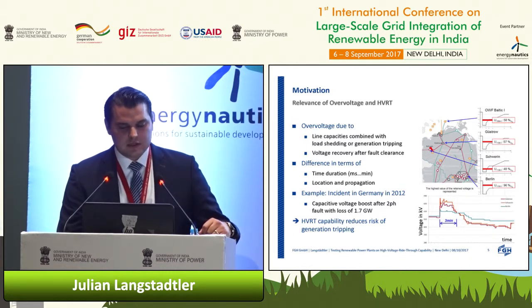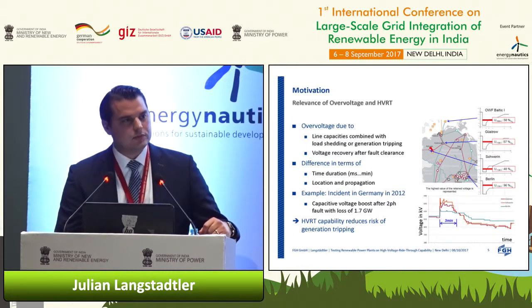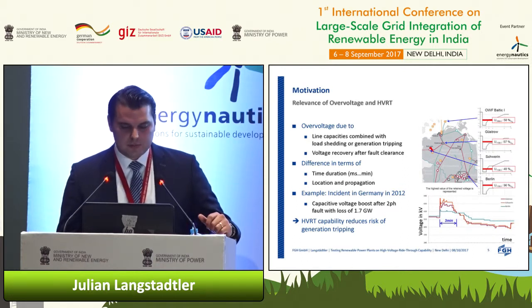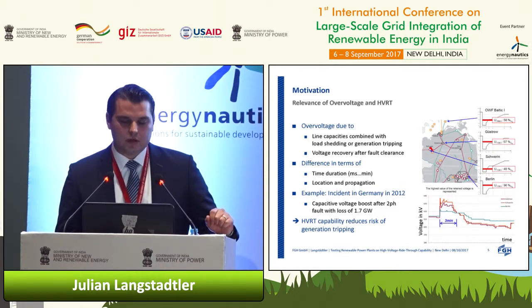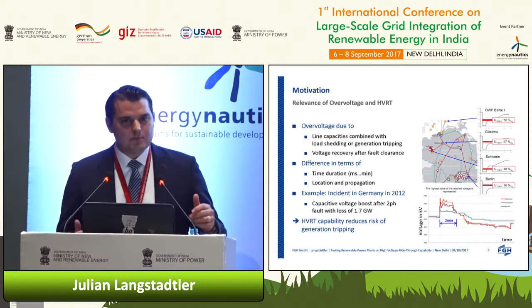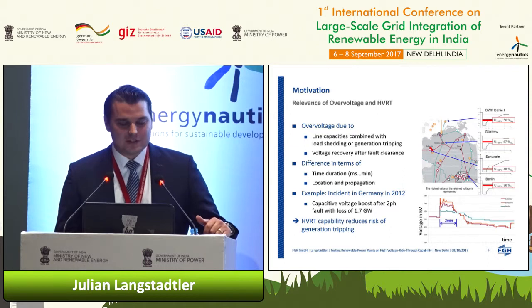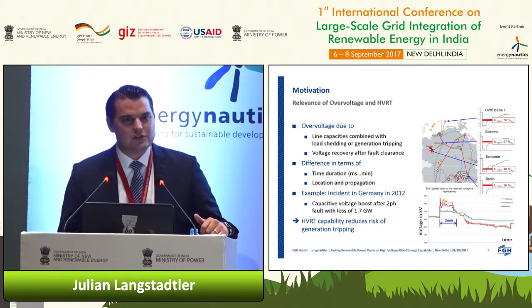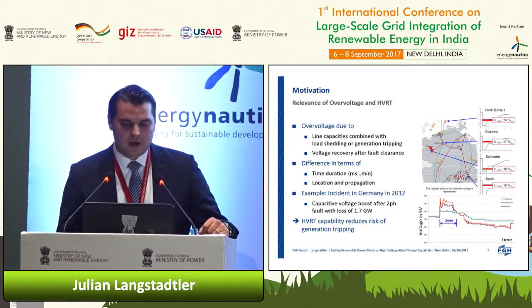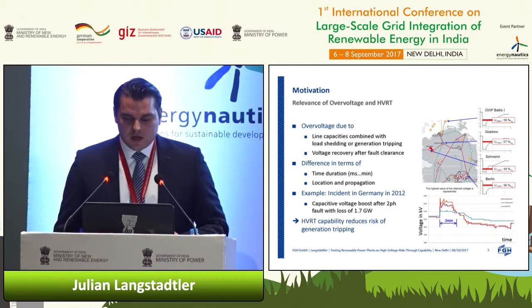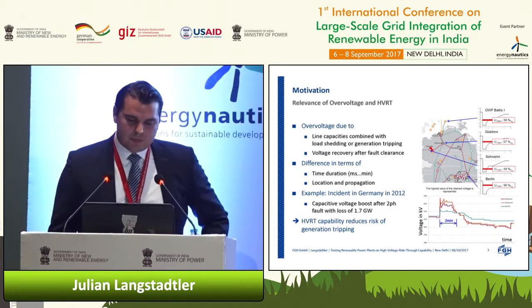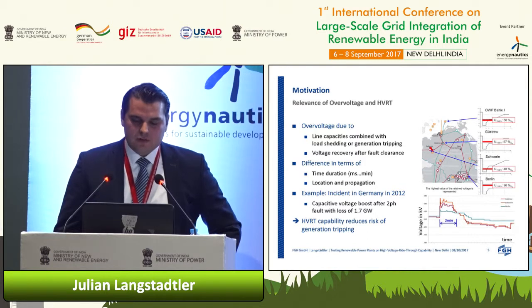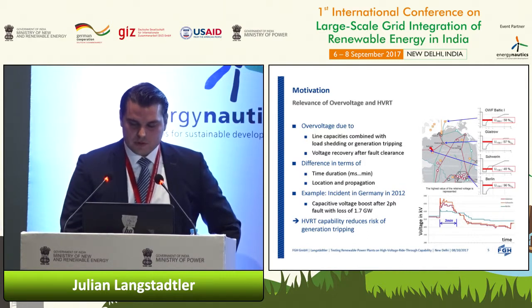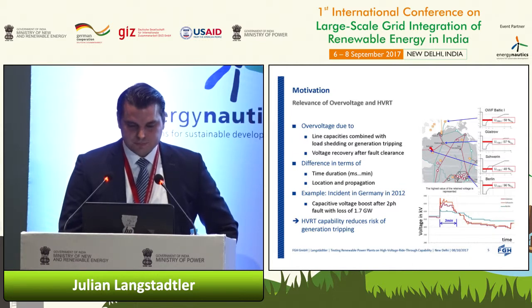And in the end, we had the problem that almost 1.7 gigawatts of installed wind power capacity was disconnected at that time. And it may not seem much for Indian standards, but for this grid section in Germany, this is a very significant amount. And if there was the requirement for HVRT, it would have been a better effect in this regard. So you see here also the overvoltage that happened in the high voltage system.